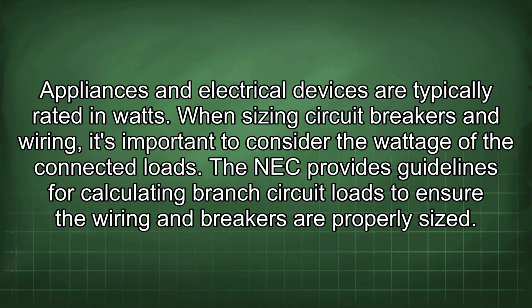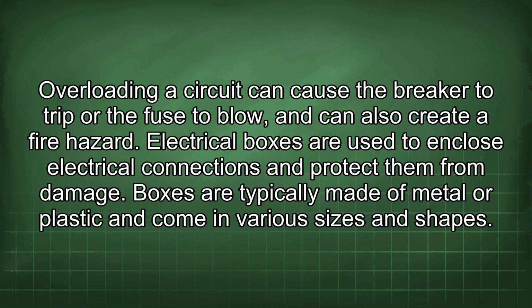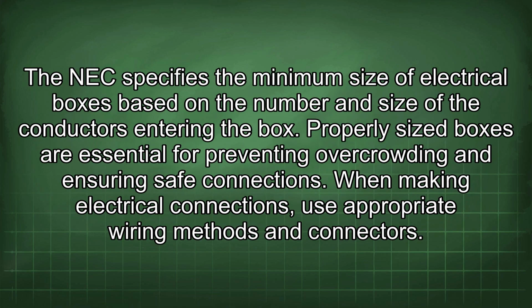When sizing circuit breakers and wiring, it's important to consider the wattage of the connected loads. The NEC provides guidelines for calculating branch circuit loads to ensure the wiring and breakers are properly sized. Overloading a circuit can cause the breaker to trip or the fuse to blow, and can also create a fire hazard. Electrical boxes are used to enclose electrical connections and protect them from damage. Boxes are typically made of metal or plastic and come in various sizes and shapes. The NEC specifies the minimum size of electrical boxes based on the number and size of the conductors entering the box. Properly sized boxes are essential for preventing overcrowding and ensuring safe connections.